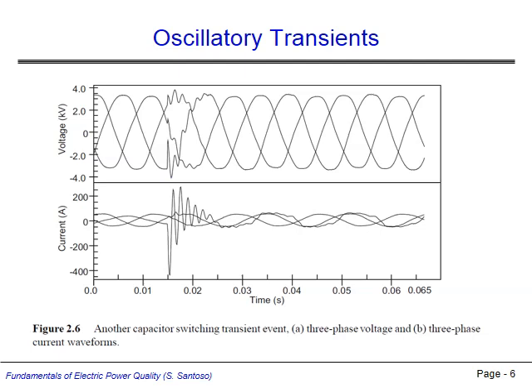This figure shows another capacitor switching transient, this one showing the effects on all three phases. The switching occurs at about 15 ms, causing a large oscillation in the current of one phase, along with significant oscillations on all three phase voltages. These oscillations have mostly been damped out by about 10 ms later.